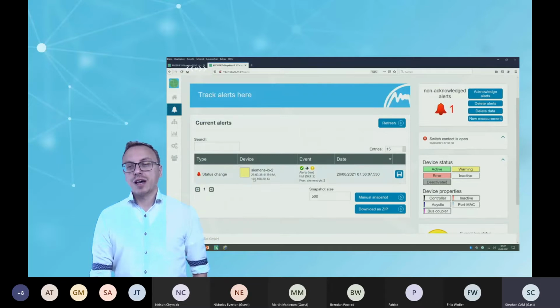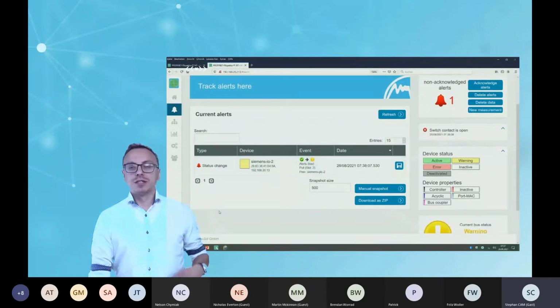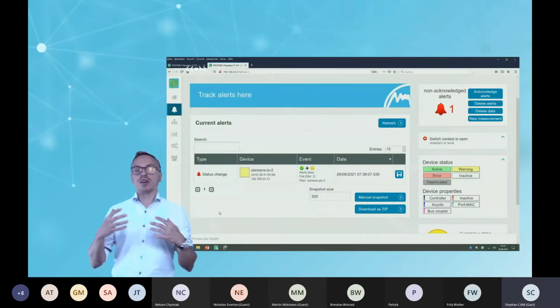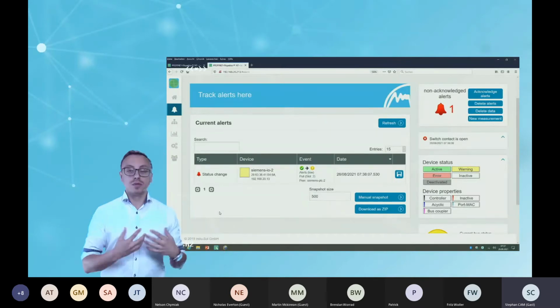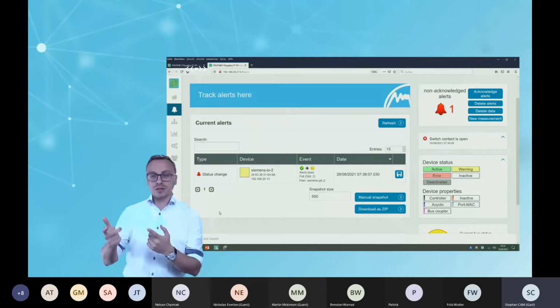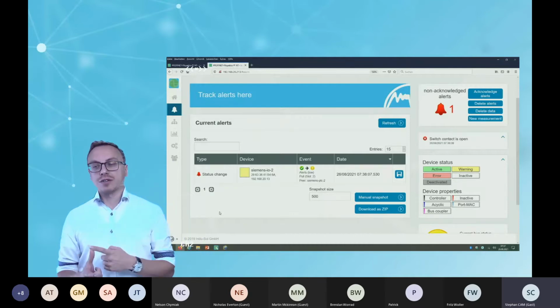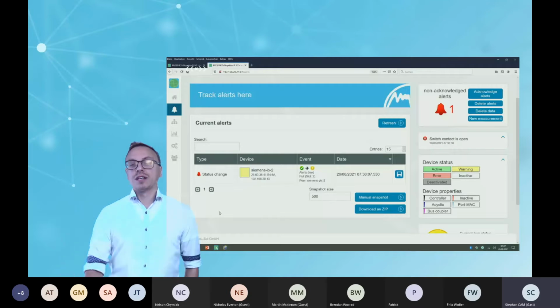we have a diagnostic message from the Siemens IO2, and here you see it is a PROFINET diagnostic with low priority. We have a pull of slot number 2 on this timestamp. This is how it works. The inspector can analyze all quality values and all normal situations in PROFINET, like diagnoses, like drop-offs, like restarts. And every time the inspector will show you what happened, which device, and at which time.